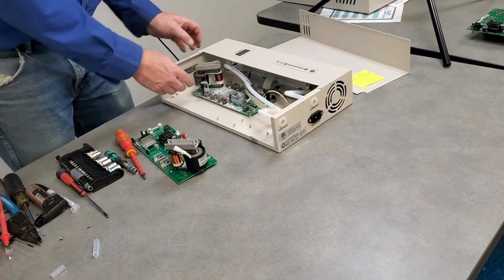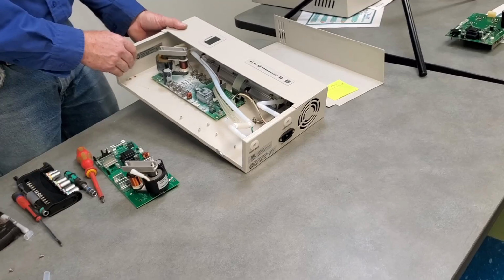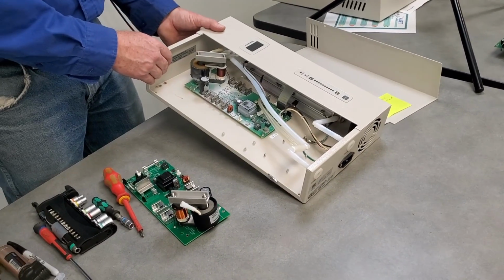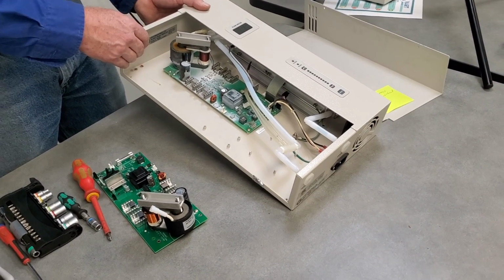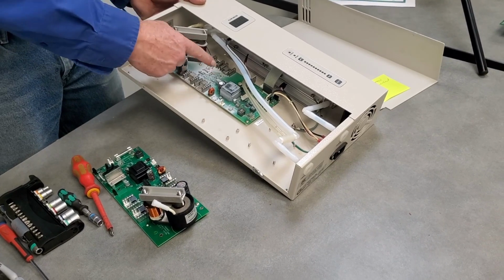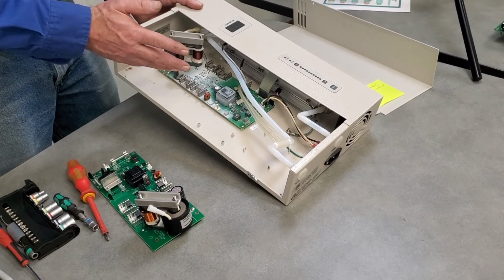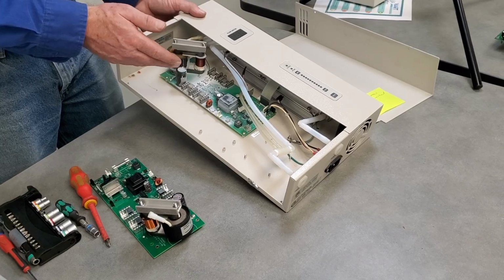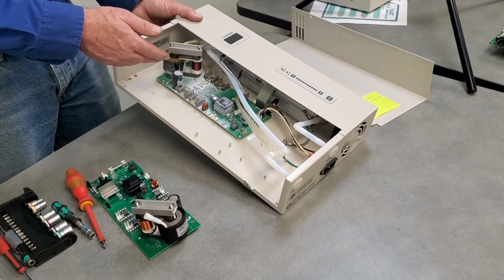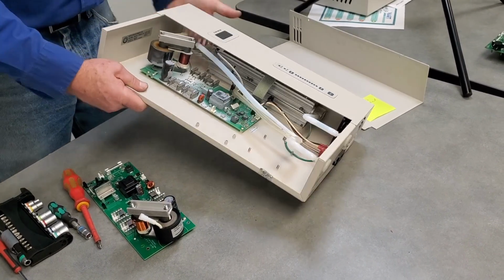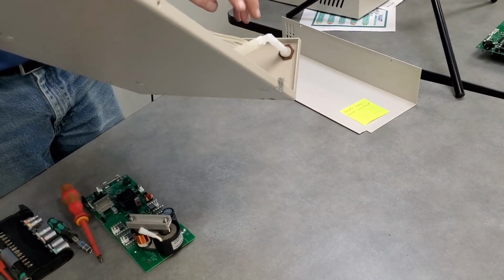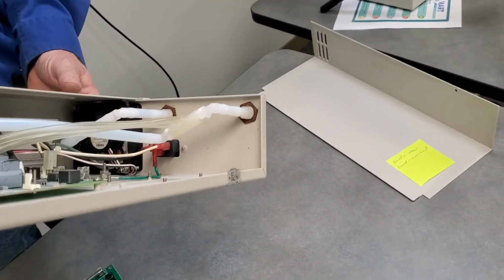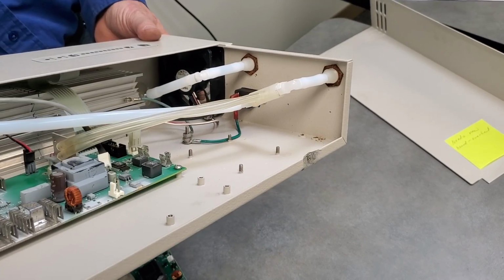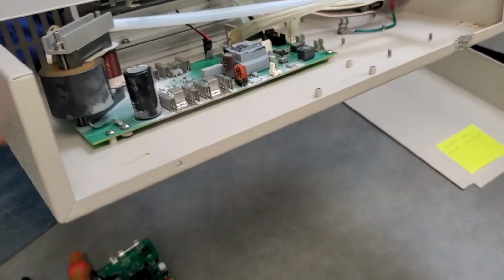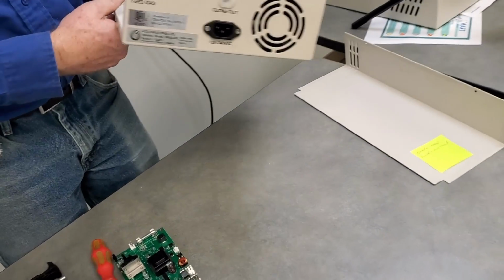Now this particular one, there's some indicators that things got too hot and they were exposed to ozone. All this white powder here, one of the things that just, the fan may have quit, it overheated, and there was some ozone in the air. You can see some other things. The fact that these nuts are all rusty means that it was probably a damp, humid environment, and once that fan quit, it started to corrode.